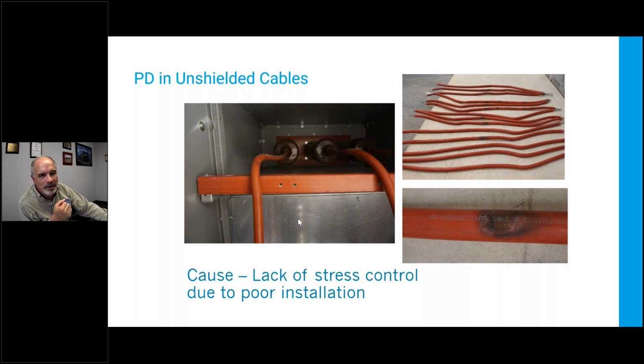And they had 13 identical cabinets, and you can see every one of them was discharging. Here's the cable. This is after about 4 months of operation. This would not have lasted a couple of years. But again, a lot of people looked at this and said there's nothing wrong with that, including the switchgear manufacturer. Nothing wrong with that installation. It's because we're not used to it. We don't use it all that often. That's what they have.